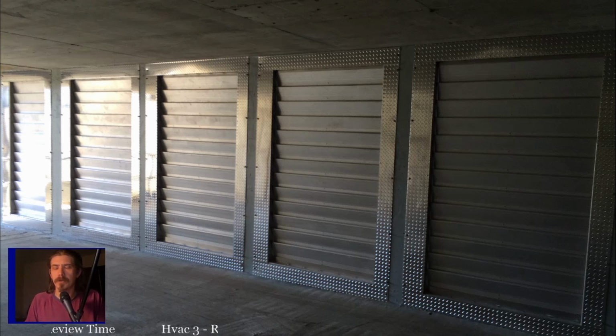So that's what it actually does in most air handlers. But on your exam, it gives you another reason, but it's equally important to make sure you understand. When you have separate sets of contacts on a fan relay, the other reason you'll have that is because if you remember when we talked about motors, one thing that's very important with motors is you cannot energize two speeds at the same time. So if you're setting up multiple speeds for whatever reason, say you wanted to have an air handler that had a lower speed for heating than it did for cooling, and you were going to set this up yourself. You need to interlock those speeds somehow so only one can come on. You don't want to have a relay for high and a relay for low, two separate relays that could somehow, when something else fails, energize two speeds at the same time because you're going to burn the motor up like that.